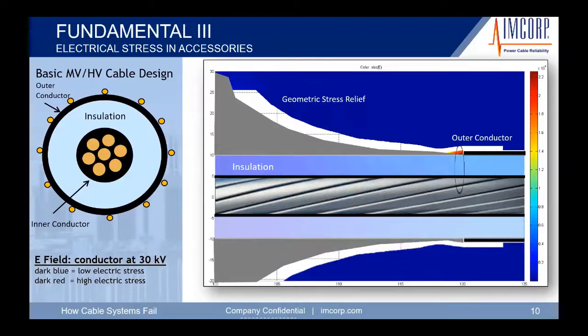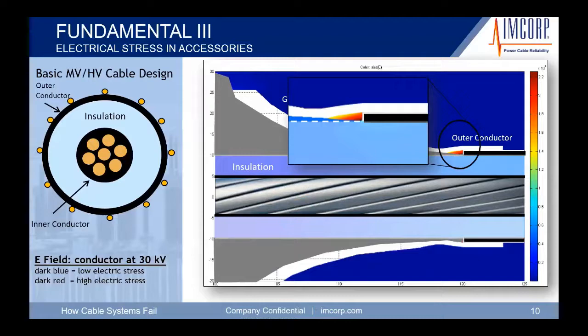So here is an example of a void filler. We've got to put a smooth transition in there so that when the field comes off of the semicon, it's a smooth transition. So there's no big step downs, no air voids, so that air can ionize.